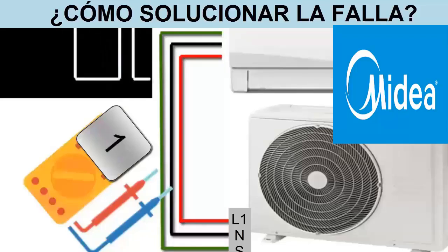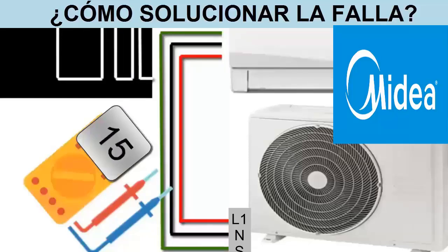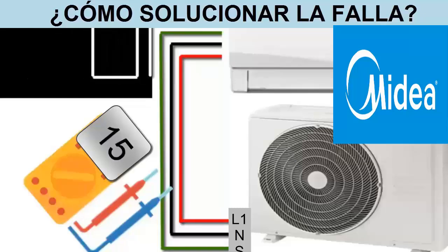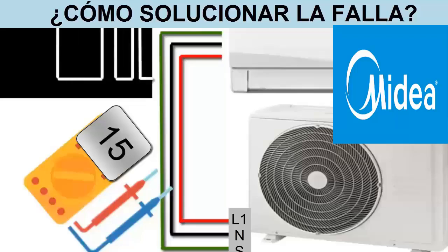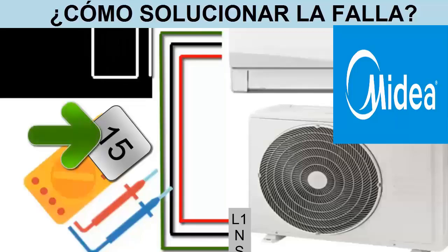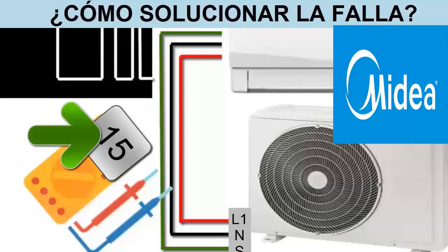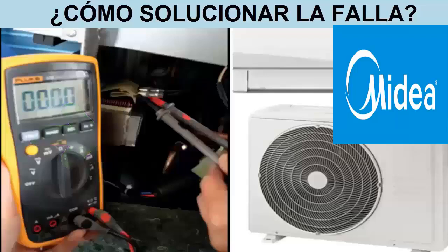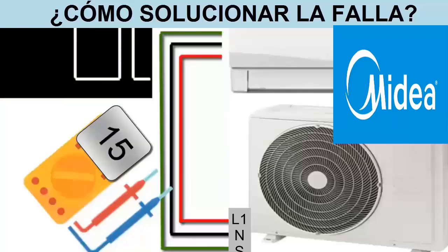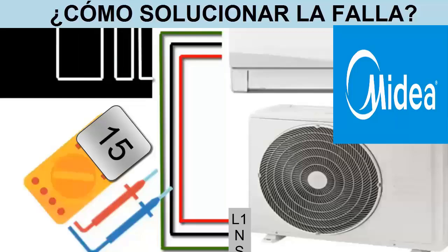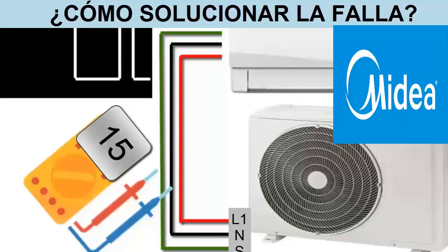8. For other brands of air conditioners, with a different data transmission protocol, when the unit is operating normally, the voltage measured on the signal wire always fluctuates between positive values. 9. As a general rule, if any electronic control unit is not functioning correctly, the voltage values measured in the previous step will always be constant.